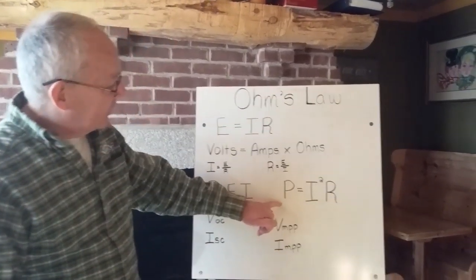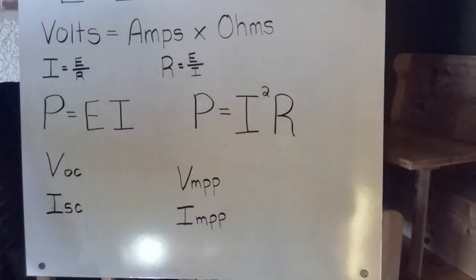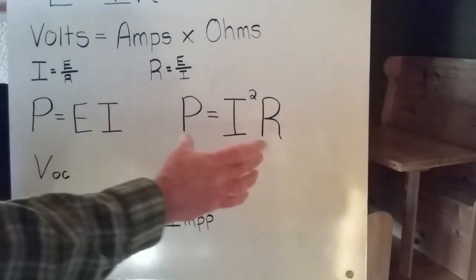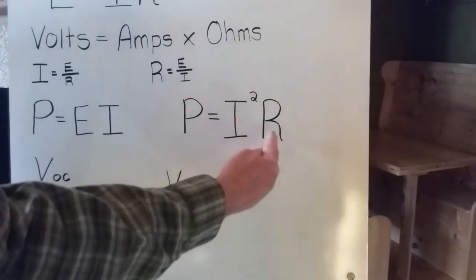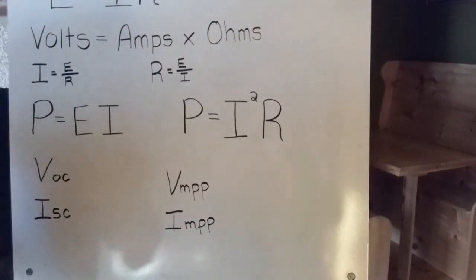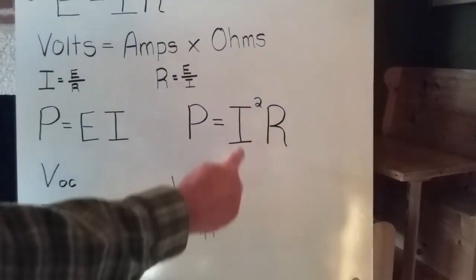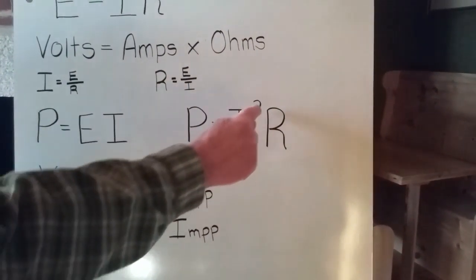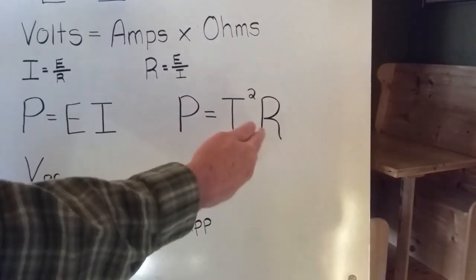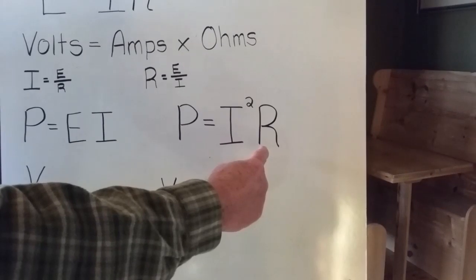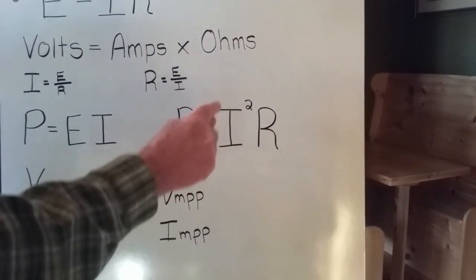Now let's go back and look at our P equals I²R. Remember we said we can't get away from that resistance. So what's going to happen here is we're going to lose power to our resistance, to our little vampire loads that are sucking power away from us. But how do we minimize that? Well, you can see that we're going to square the I, whereas R is more or less constant. There's probably not much you can do about it. It's the length of the wires and the size of the wires. You can put in bigger wires to reduce R. But what you really want to reduce is I.